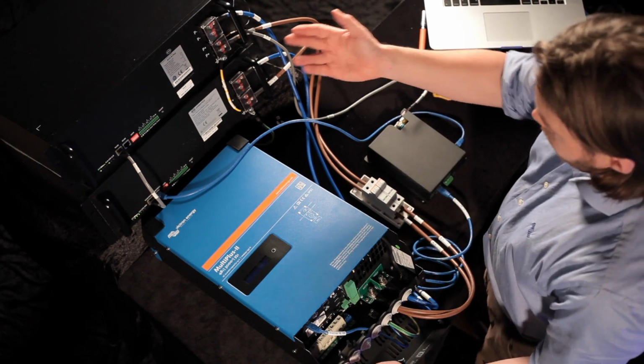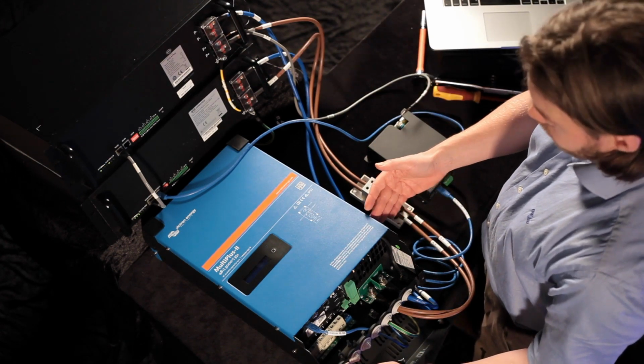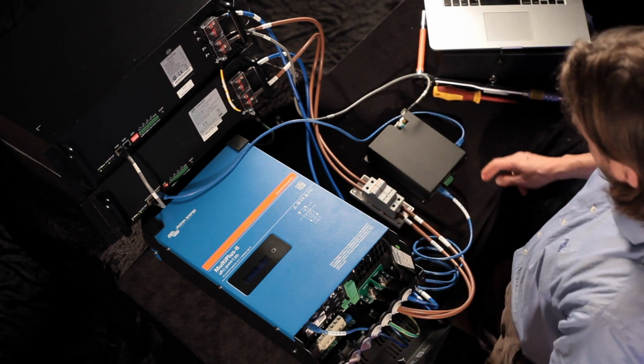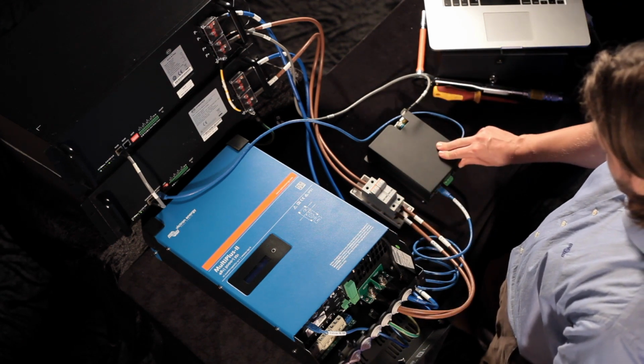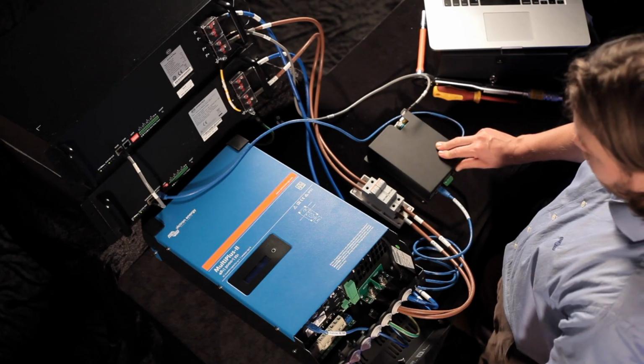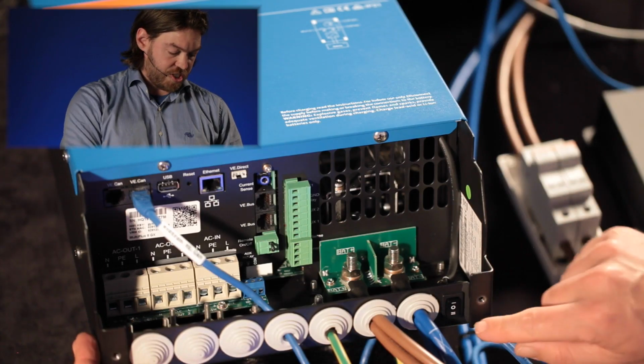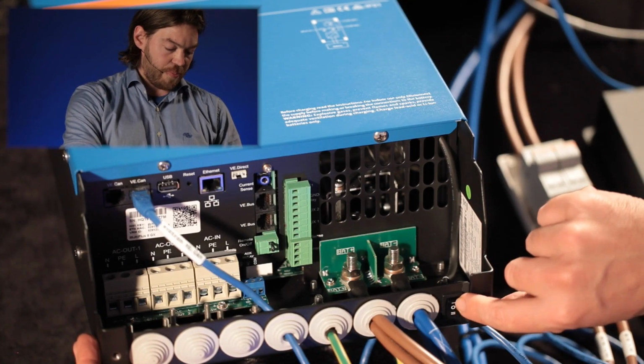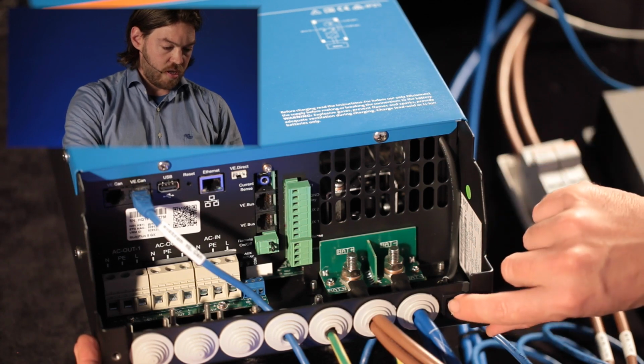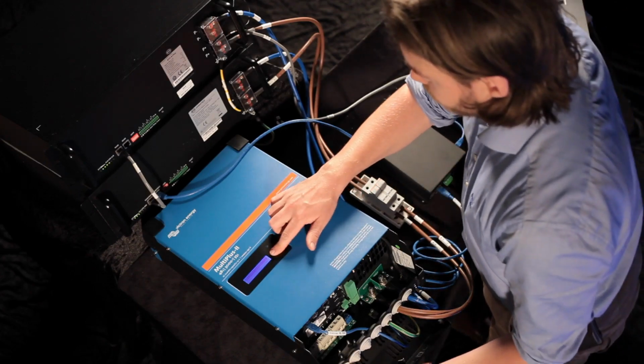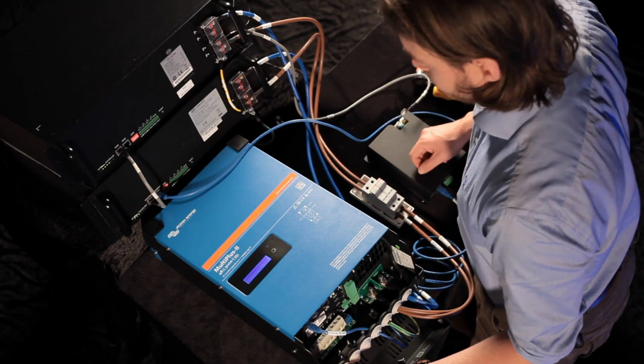This has now powered the system. It's providing charge to the capacitors. My BMU is now powered on. When I use this switch at the bottom and switch it up towards the front of the unit, the MultiPlus 2 will turn on. The unit's turning on, we can see the screens come on, I can hear it humming, and we're now ready to start commissioning.